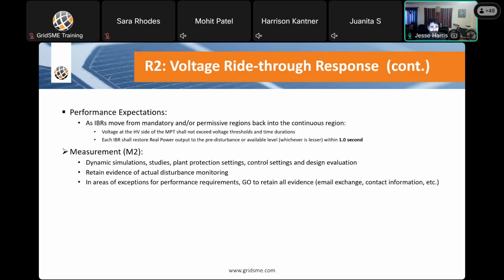And performance expectations. So as IBRs move from that mandatory or permissive region back into that continuous normal operation region, essentially you can't have heavy overshoots that are going to push the high side of the main power transformer outside of its voltage limits. And then when they do come on and they restore real power, it needs to be restored to pre-disturbance level or the available level, whichever is less, within 1 second.